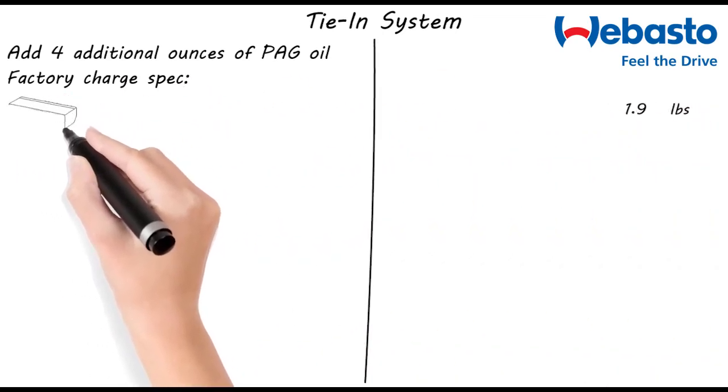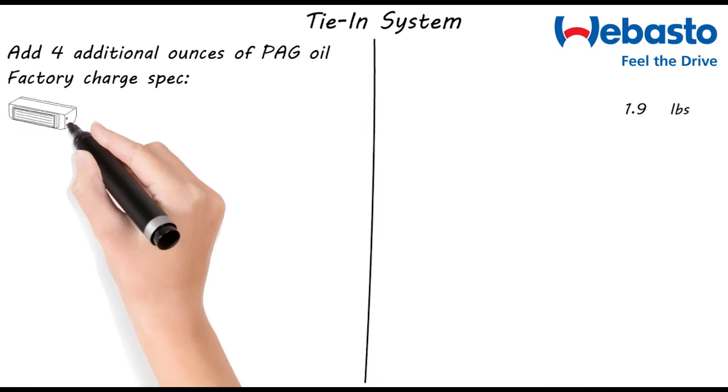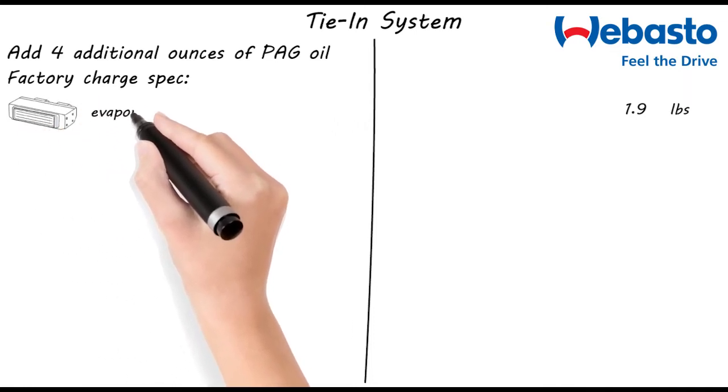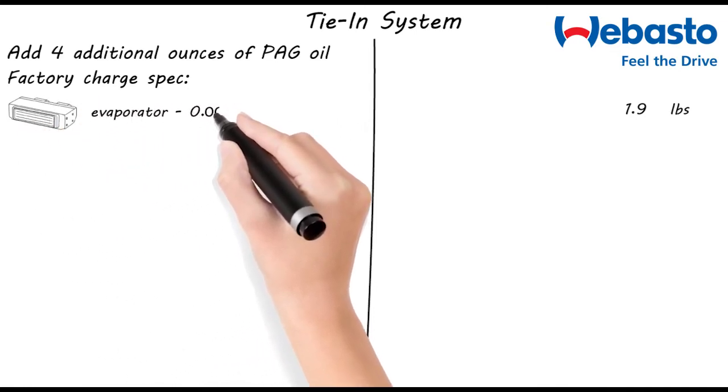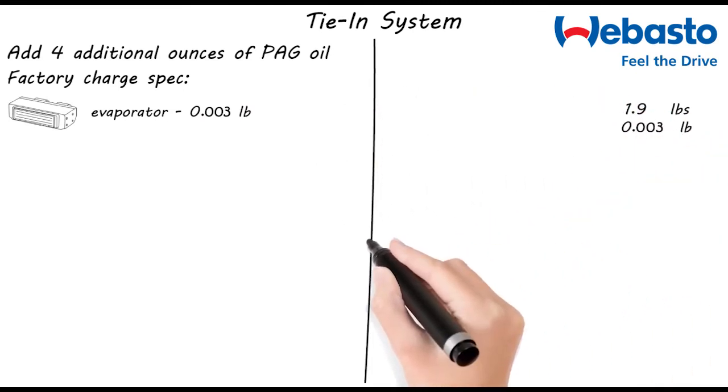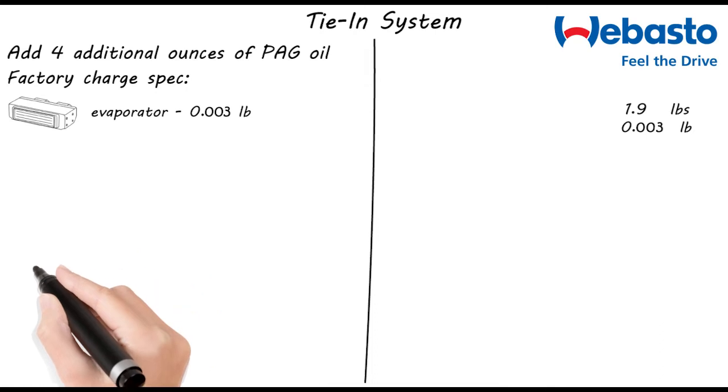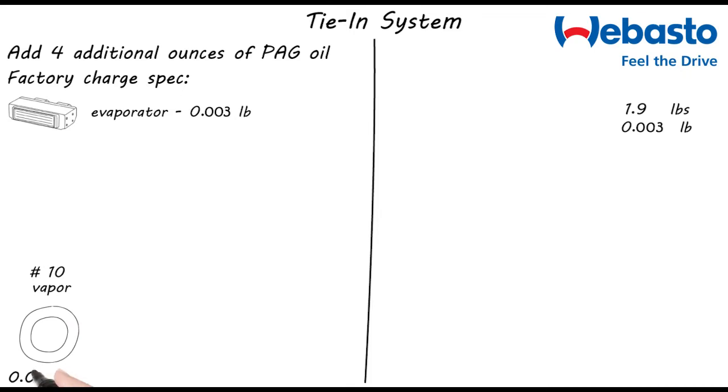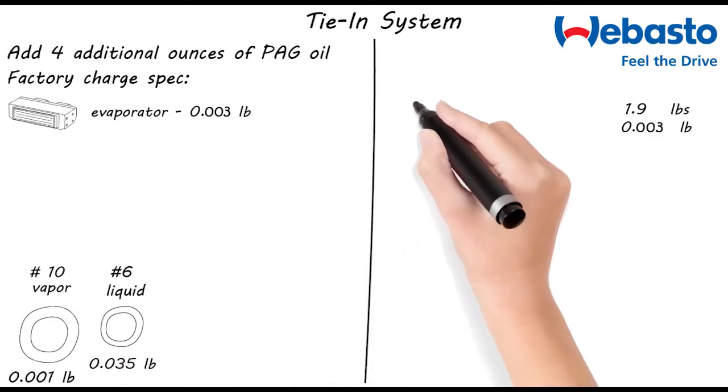Each component in the system will require a certain amount of refrigerant to be added. In this system, the evaporator will require 0.003 pounds of refrigerant. We'll put that over here with the factory charge spec for later. The next consideration is the length of hose used in your installation. We'll add 0.001 pounds per foot of number 10 hose on the vapor side and 0.035 pounds per foot of number 6 hose on the liquid side as an example.